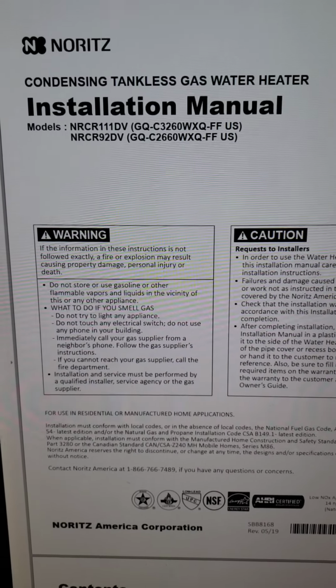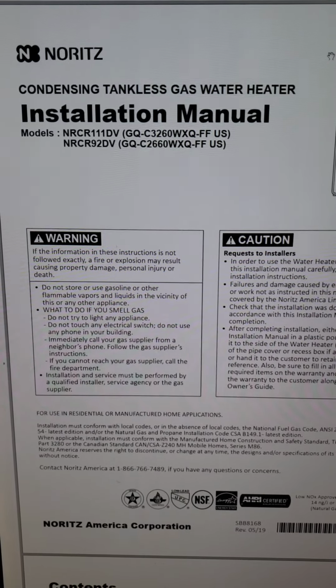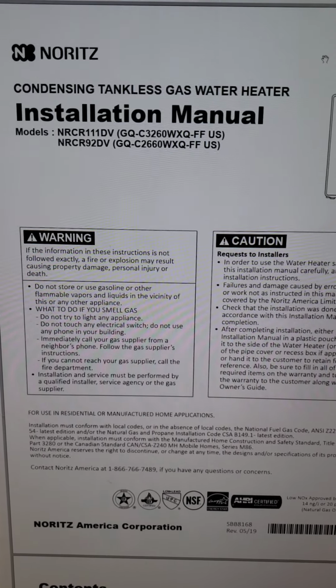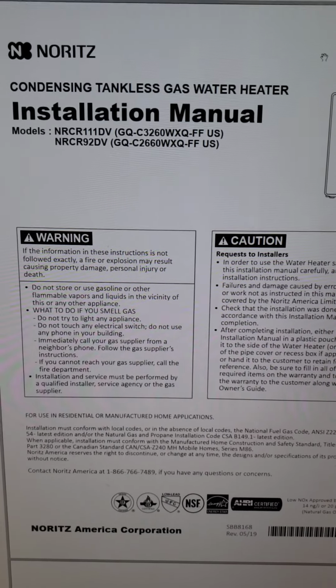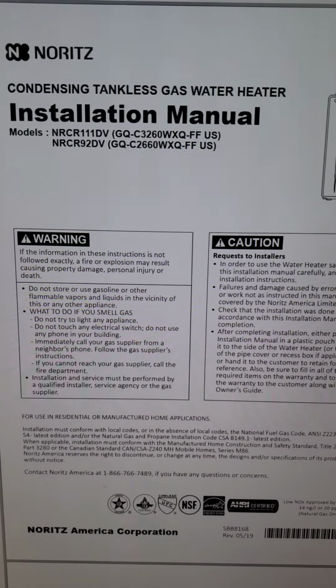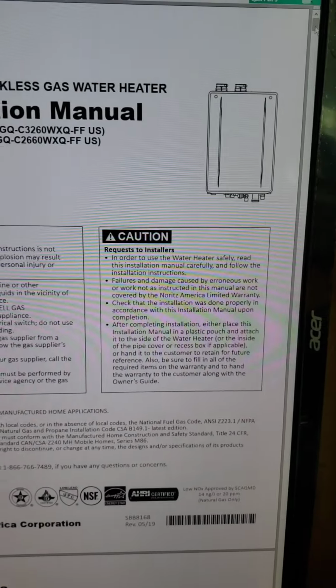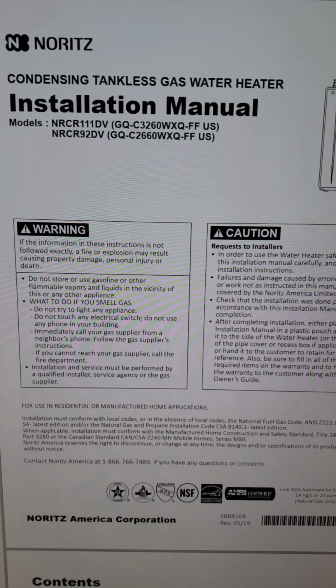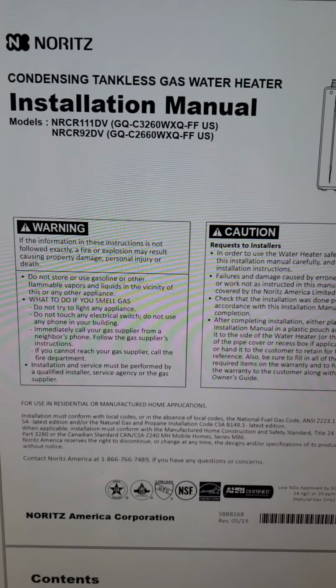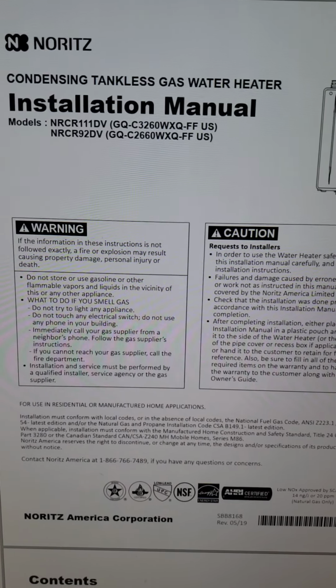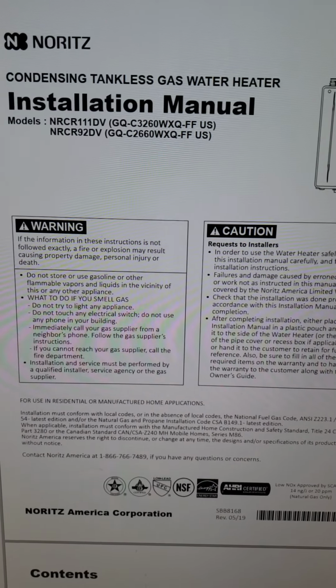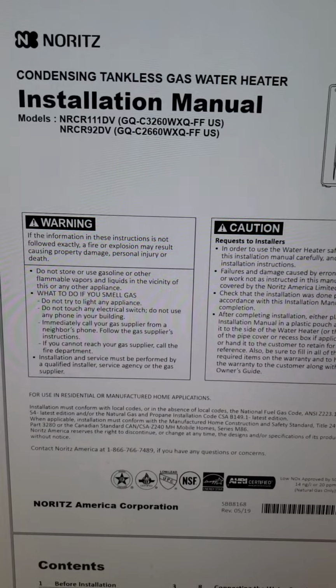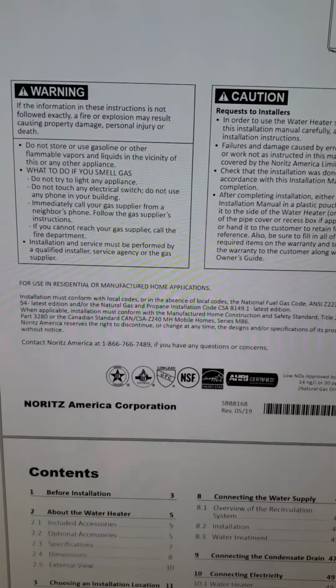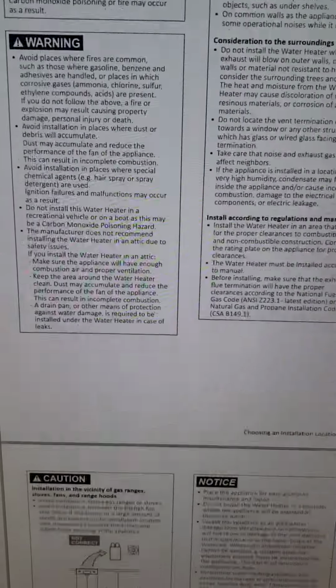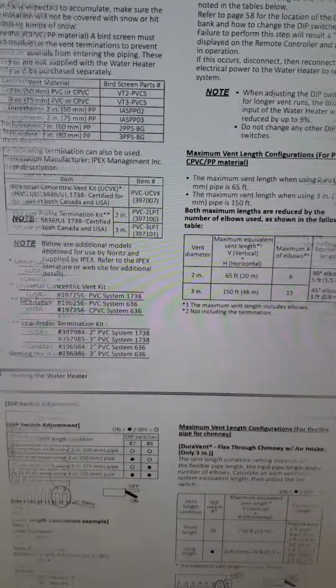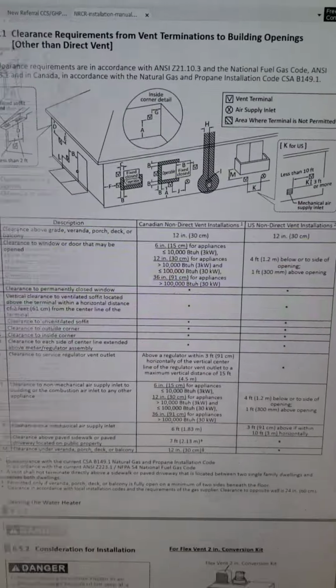I would like to talk about error code 63 on Noritz recirculating tankless water heaters. These are the model numbers that we have, but you may have a different, similarly equipped water heater. This water heater has a recirculating function, meaning there's a separate circuit where water circulates around your supply system so that when you turn on the water, it's hot instead of having to wait for the water to travel through the entire system.